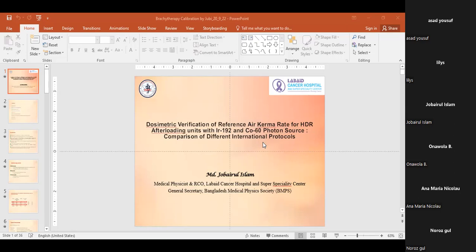For these three measurements, one is the well chamber, another is free in air, and another is the solid phantom. In this, according to the protocols, DGMP 6809.2, TG 43 and IAEA TECDOC 1274, they mention a minimum of 1 meter distance from the source, from any wall or floor, due to scattering, to avoid attenuation of dose, and also to avoid uncertainties.